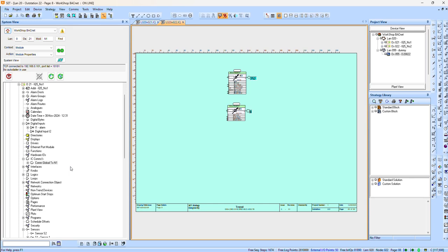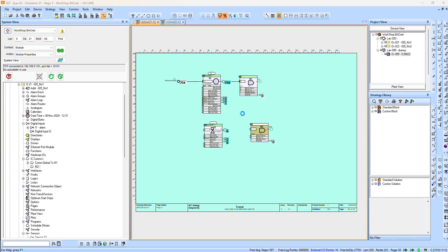So you do need to make sure the priority is correct. Otherwise, you will end up with fighting priorities. There's 16, lowest number wins. My set rights were at a different priority to mine. So that's it essentially, and the process is very similar for the binary information. You would use exactly the same dummy address to do it.